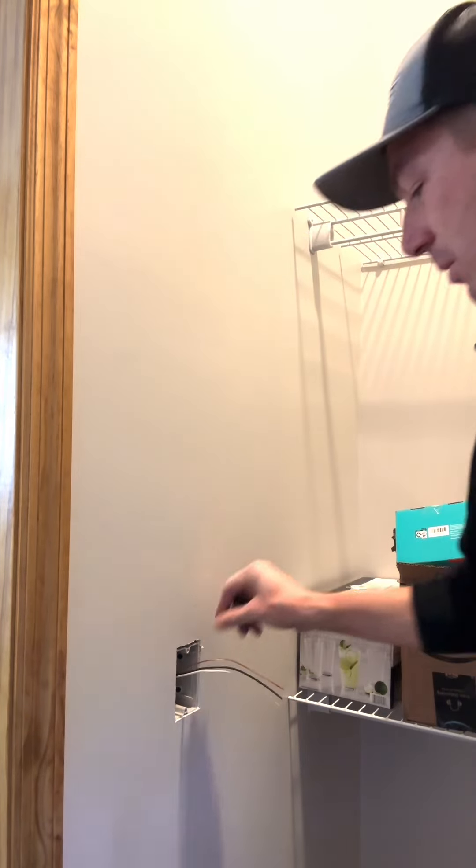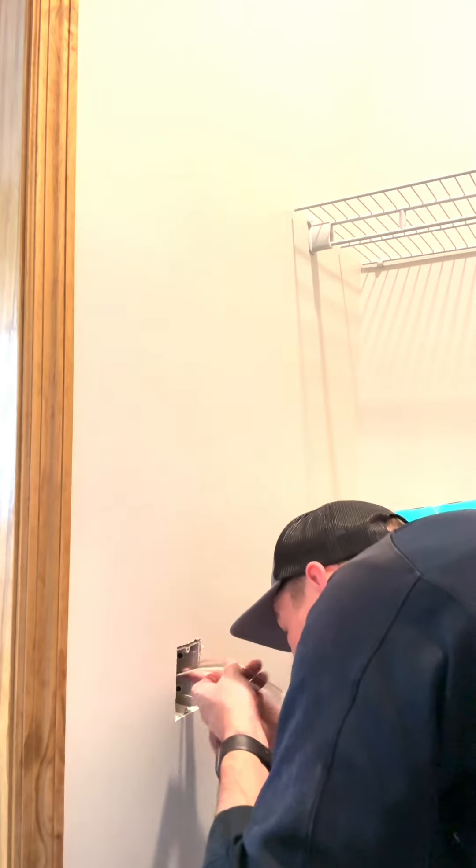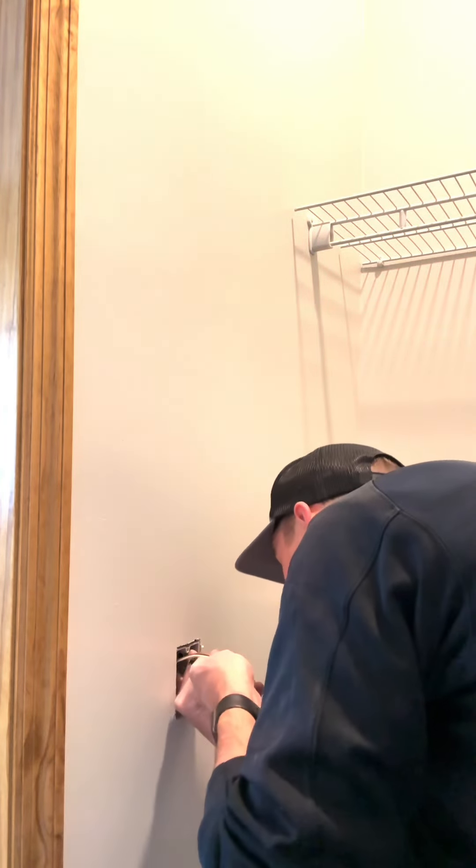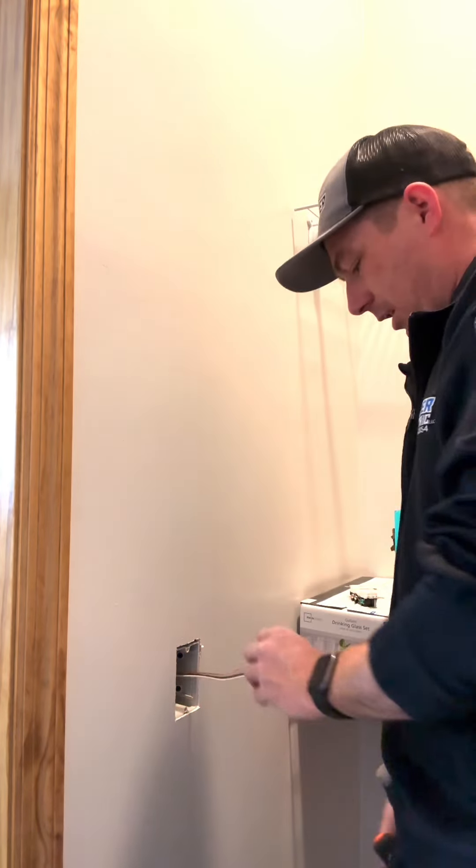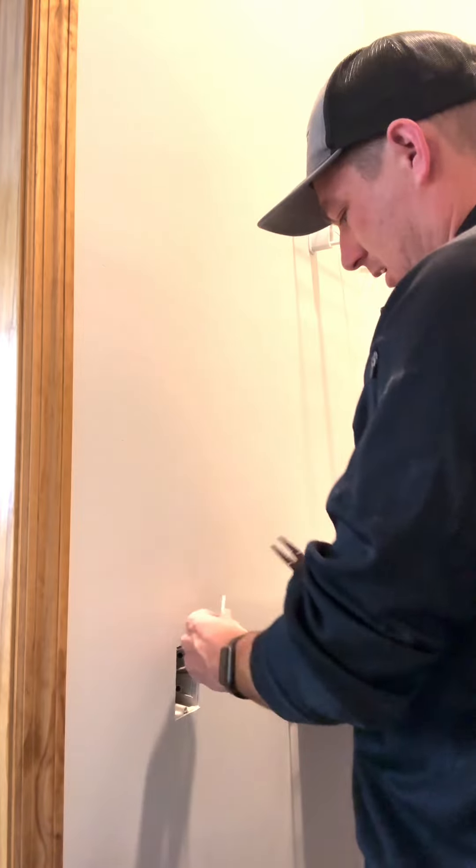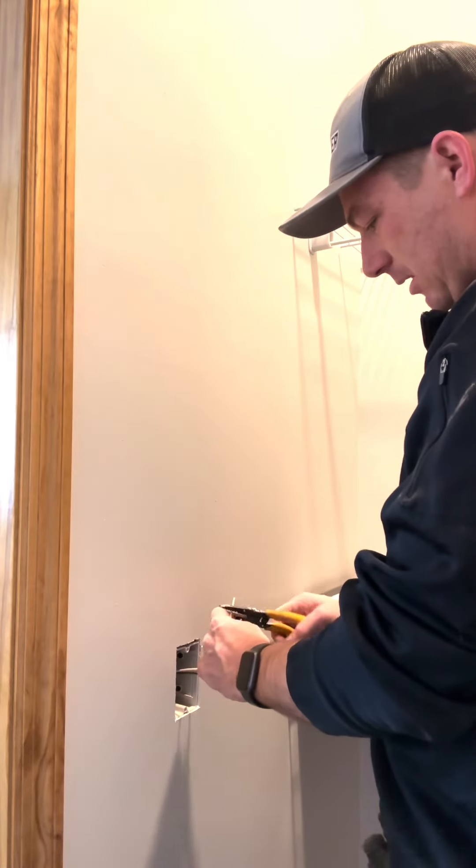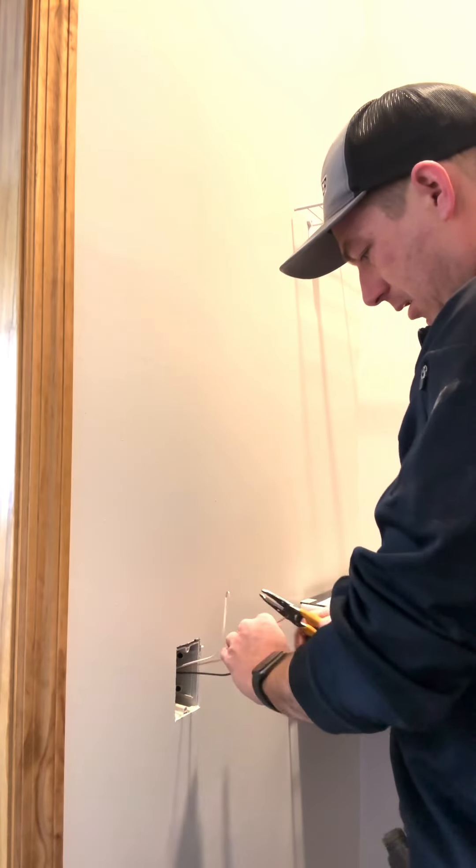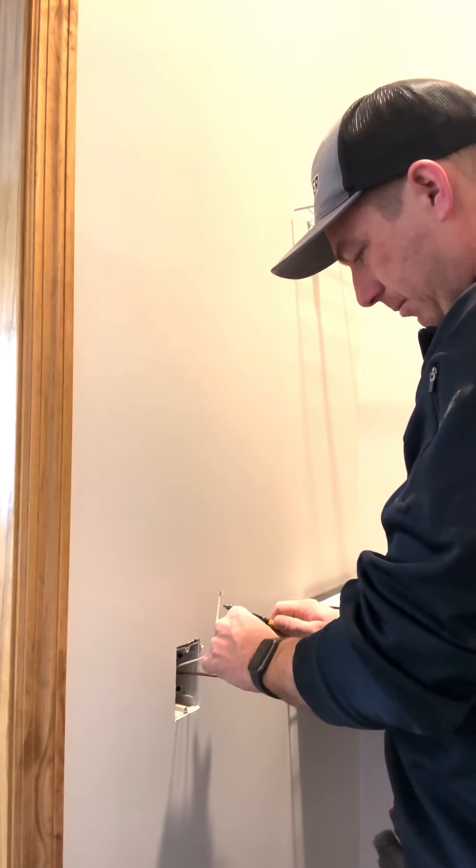And that is why that box is awesome. You always want to make sure your insulation's sticking in there about a quarter inch, which it is. Now I can make this outlet up, strip about an inch off, make loops.